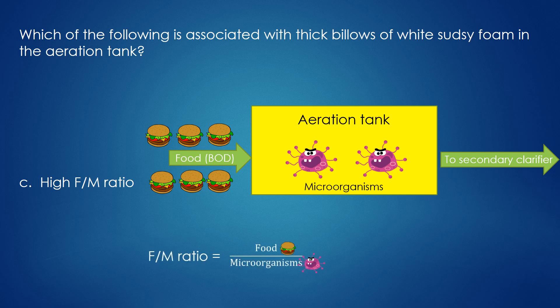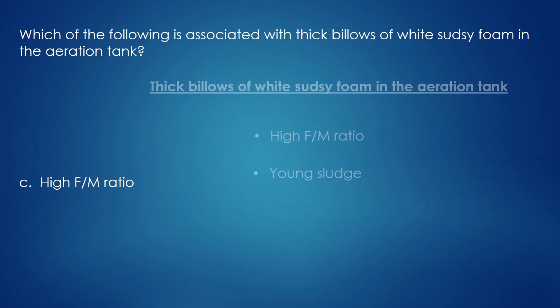If we were to calculate the FM ratio for this scenario, the quantity of food that goes into the top of this formula will be large, but the quantity of microorganisms that go into the bottom of this formula will be small. When you do the math, this leads to a high FM ratio, which is associated with thick billows of white sudsy foam in the aeration tank. Another characteristic of this condition is that the aeration tank has young sludge, meaning the microorganisms haven't spent a lot of time in the aeration tank. So remember, thick billows of white sudsy foam is associated with a high FM ratio and young sludge.